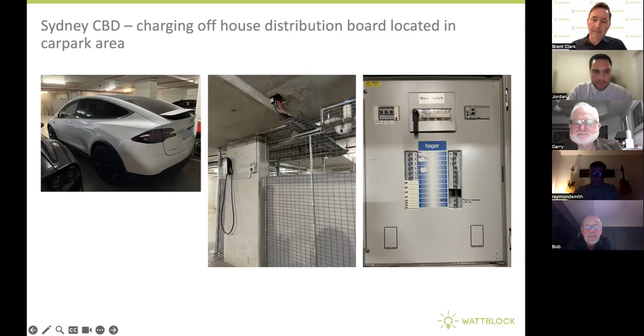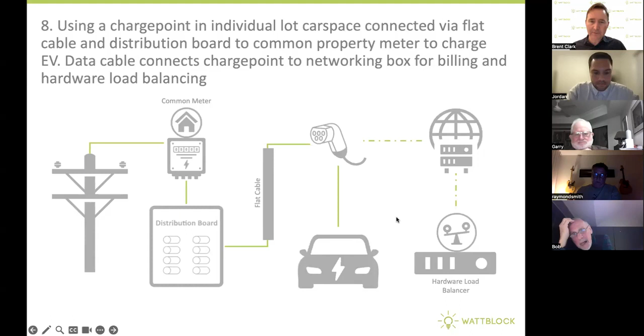Model number 8 uses a charge point, again an example of an EV charging infrastructure backbone providing charging into all the individual lots. It's similar to the last two models, but instead of a cable tray running cables to the charge points, we use a product called a flat cable, sometimes called a bus duct or bar cable, and you can hang multiple charge points off this flat cable. Let's show a picture of what that looks like.